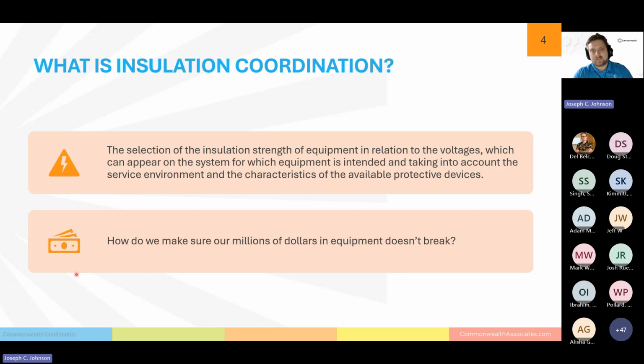What does that really mean? That means, how do we make sure our transformers and breakers and buses that cost millions of dollars and take months and months or years to install and procure, how do we make sure we don't break those because of system conditions? The system out there, a 115 kV line doesn't stay at 115 kV all the time. There's all kinds of stresses, lightning strikes, switching surges, as well as faults and voltage rise and fall because of those things. It's anything but static. It's these extreme events. How do we make sure our equipment is protected?